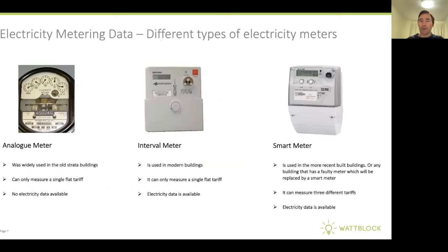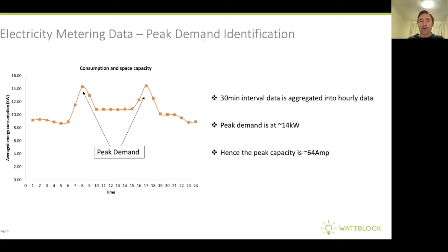On electricity metering data, we've got three different types of electricity meters. On the left is the analog meter — the oldest, which is getting phased out. In the middle are interval meters, quite common in our strata buildings. And on the right are smart meters, what we should all be working towards. Electricity metering data allows you to identify peak demand. If we graph electricity metering data coming in at 30-minute intervals, you can see on this graph there are two peak demand points at 14 kilowatts, appearing at 8am and just after 5pm. We can tell the peak capacity is 64 amps.